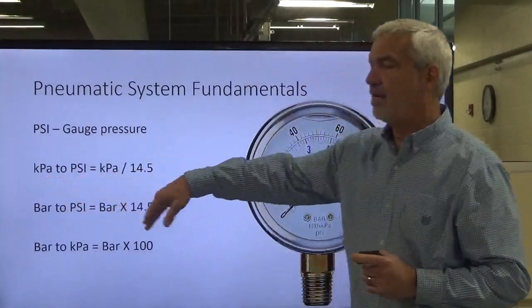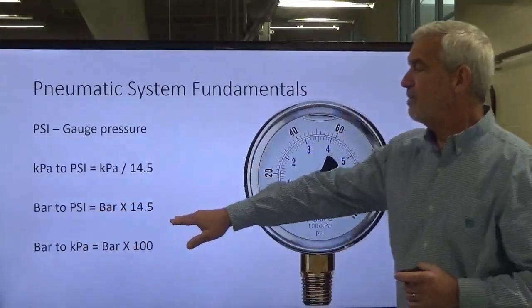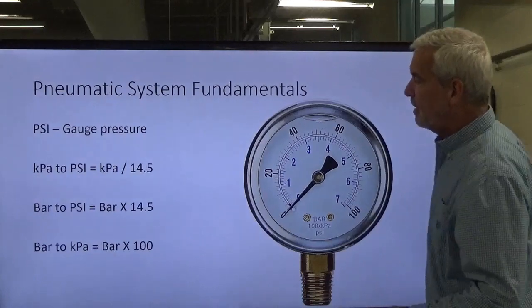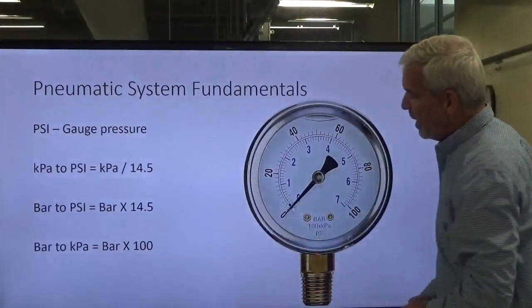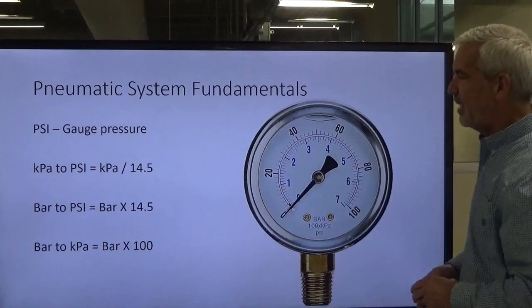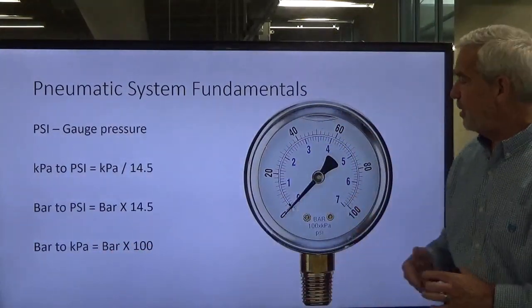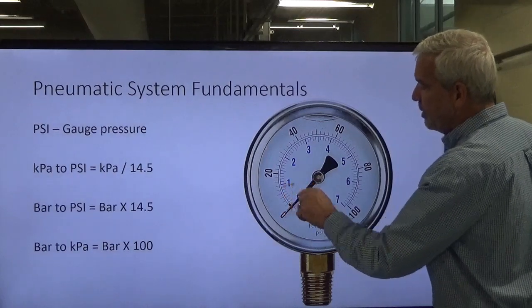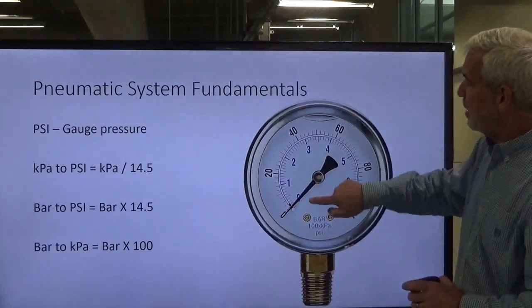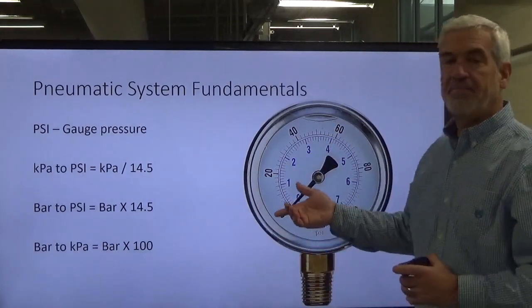Here are the conversion scales. To convert kilopascal to PSI, divide the KPA by 14.5. To get bar to PSI, multiply bar times 14.5. For example, if you had one bar, multiply one times 14.5. Bar to KPA is simply the bar times 100.